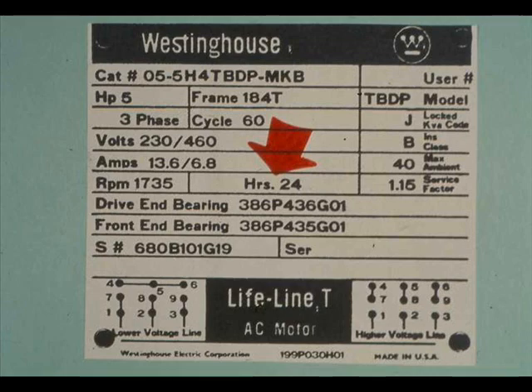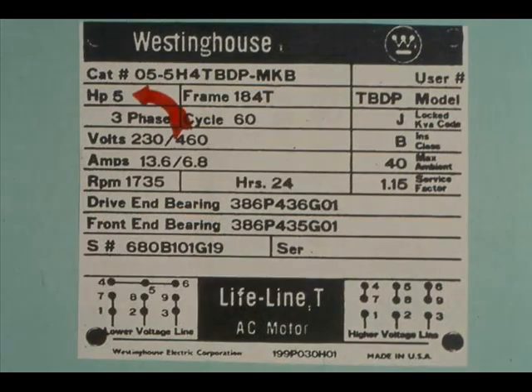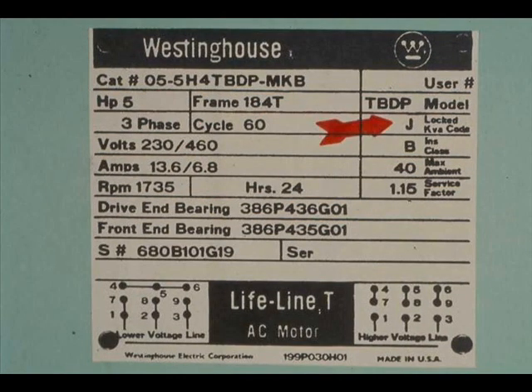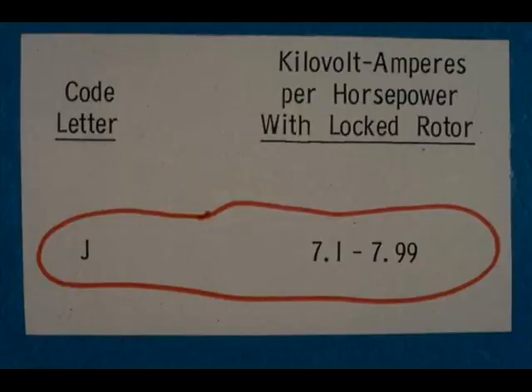On some nameplates this rating is listed as 'time'; on others, as 'duty.' Rated horsepower is a required listing for all motors of one-eighth horsepower or higher — this motor is rated at 5 horsepower. KVA means kilovolt amperes. The locked KVA code is an indication of the power per horsepower drawn from the electric power lines at the instant the motor is started. The code letter for this motor is J. The National Electrical Manufacturers Association has published a table showing codes and their equivalents; J equals 7.1 to 7.99 kilovolt amperes per horsepower.